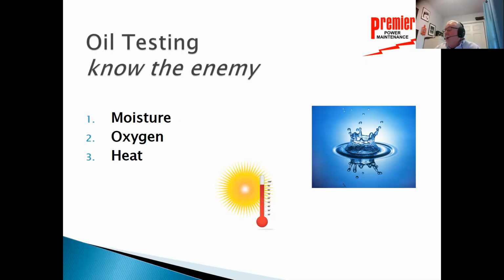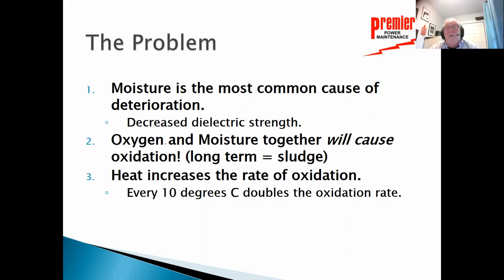First of all, we need to know the enemy and meet the enemy face to face. The enemy of this transformer is 3 main things: moisture, oxygen, and heat. If we can eliminate moisture in that transformer, make sure we don't have oxygen in that transformer, and maintain the heat level in that transformer, we've done a lot to save and prolong its life. Moisture is the most common cause of deterioration that we have. It decreases the dielectric strength of the oil, obviously, but that's not the whole problem. If moisture meets with oxygen, that's going to cause a situation that we call oxidation.